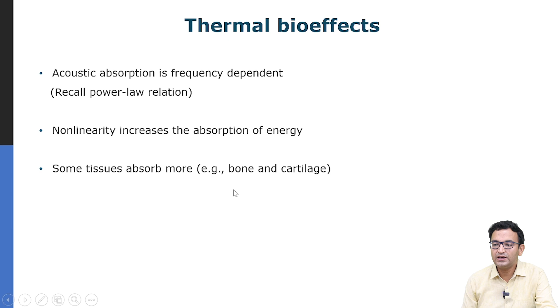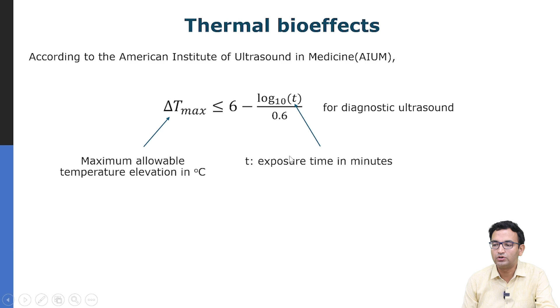According to AIUM, the American Institute of Ultrasound in Medicine, which is a professional society which provides oversight in this region, the temperature elevation, delta T max, should not exceed 6 minus log10 T divided by 0.6, where T is the exposure time in minutes. Essentially, if you increase the exposure time, then typically the temperature elevation is more. Therefore, this formula tells you that if your exposure time is longer, you will probably have to reduce your intensity or amplitude, so that delta T max remains lower than this value.